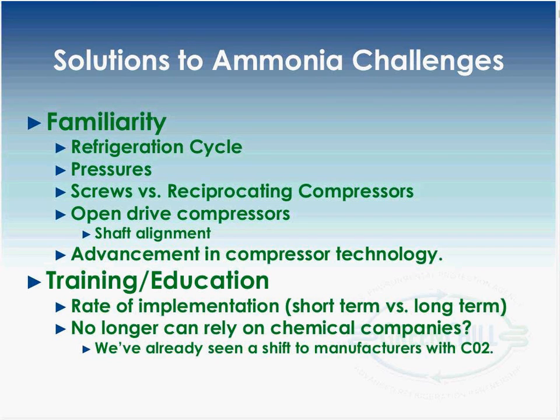The only difference, as I previously mentioned, is that they will be open drive, and it's important to note that with all the secondary systems going in now, that factor of aligning shafts is already being dealt with on secondary pumps. So that's something technicians are already dealing with. I mentioned this before too, but the advancement in compressor technology with a hermetic ammonia compressor would alleviate that.